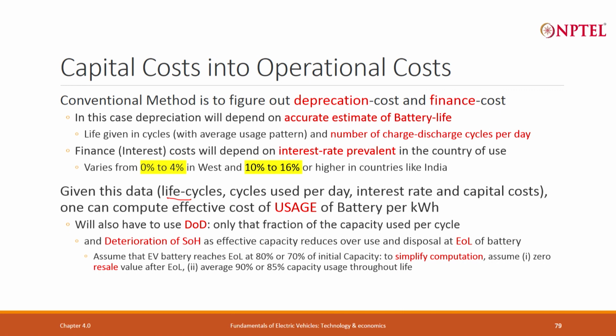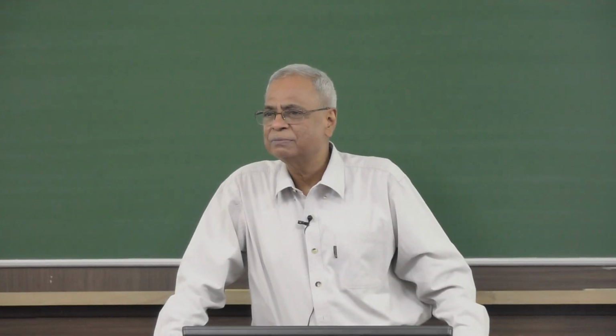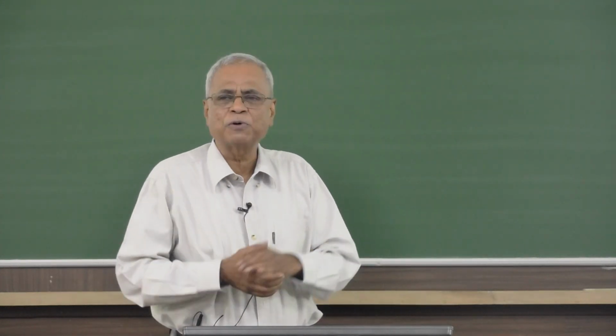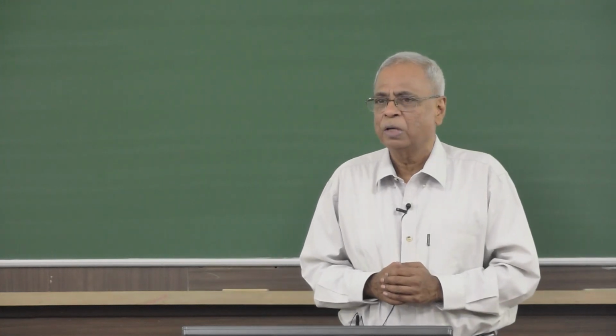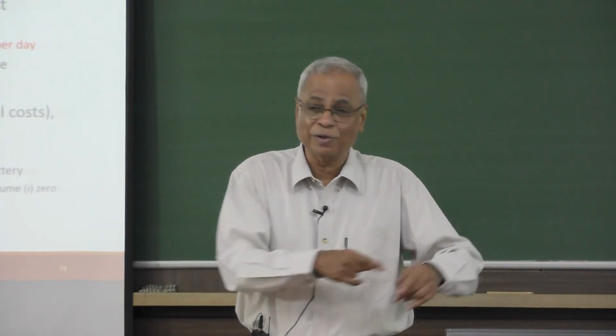So we will have to use a certain depth of discharge. Only that fraction of the electricity can be used. If your depth of discharge is 85%, you can only use 85% of the battery at a time. But it is not that alone, state of health matters too. When the battery is new, state of health is 1, and if you are using depth of discharge of 85%, suppose it was 1 kilowatt hour battery, new, so you are using 0.85 kilowatt hour. As the battery becomes old, nearly end of life, let us say state of health is 80%, so it is 85% of that 80%.